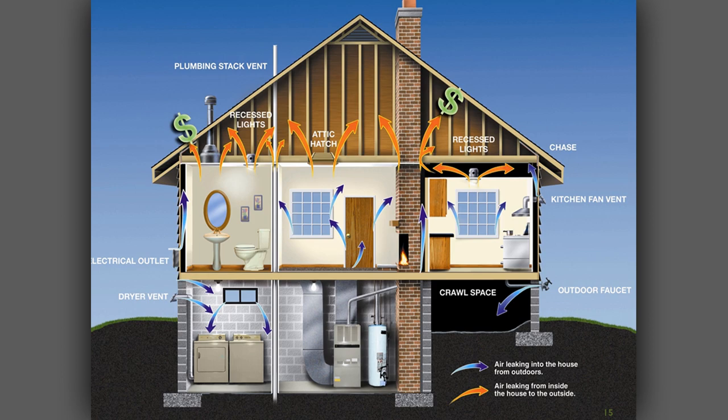Okay, so just to reaffirm, this wall could have a hole at the top or the bottom. Sure, sealing the one at the bottom might be the easiest one to get to, but we could still be leaking hot air through this wall and then out the top. So that's why we always want to seal at the top first, because we want to stop that movement of heat going through the top of our building. Take that pressure plane, as we call it, and push it farther down in the building. That restricts the amount of air that's going to come into the bottom holes.